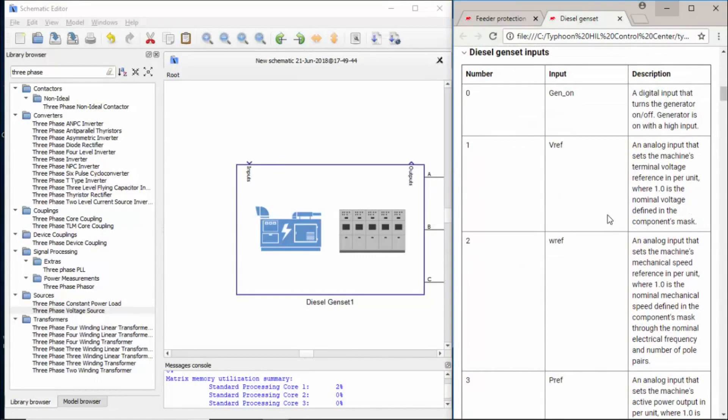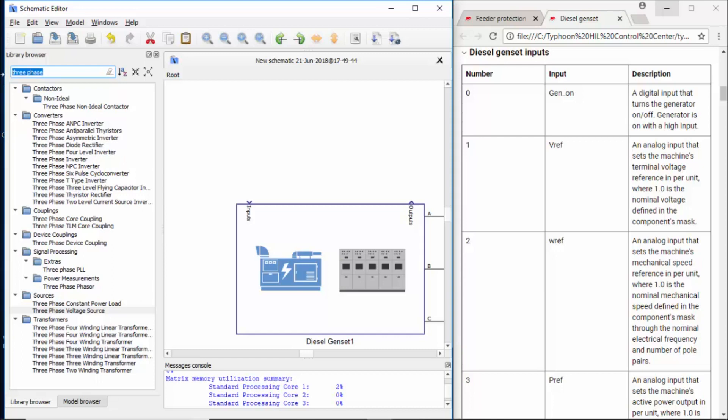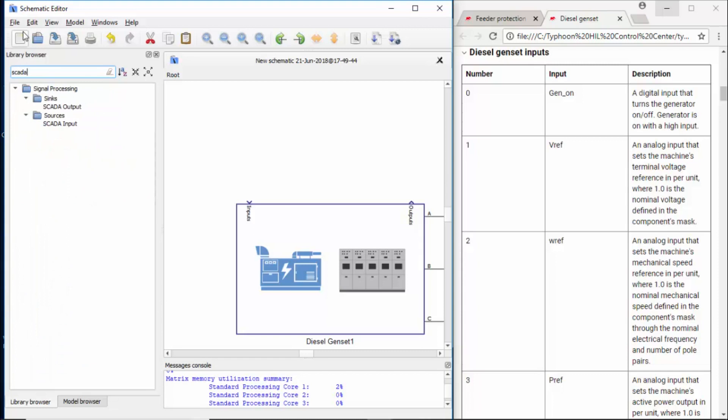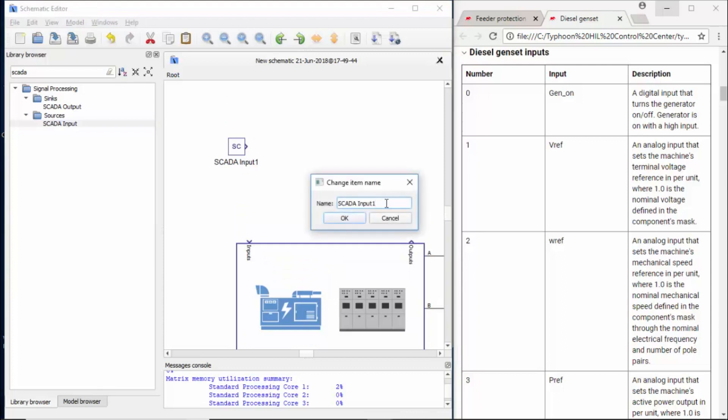On the right side, we have the inputs, and now I'll build it on the schematics. When we say inputs, it can be SCADA inputs. It can be inputs coming from other parts of your schematic. For example, you could even connect a Modbus interface device. So you can actually connect a microgrid controller implemented in real hardware. Through Modbus, you can actually control this software component, this diesel genset. Right now, we're using the SCADA inputs, so I'm just dragging and dropping SCADA inputs.